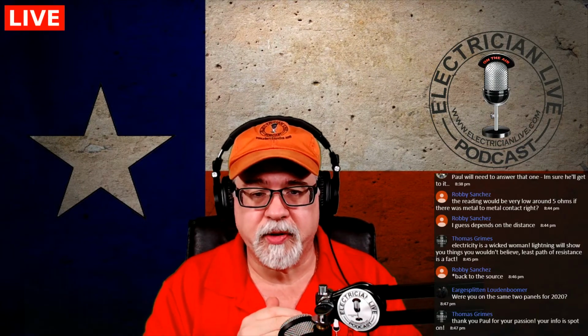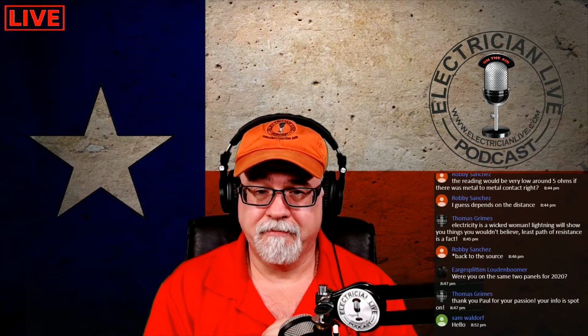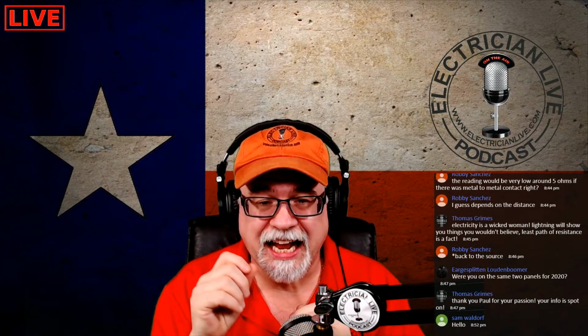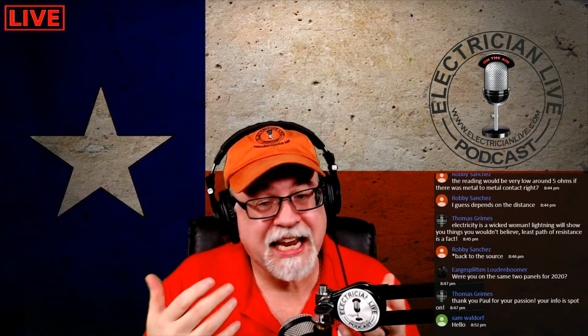I also had to do a test on NMB, and NMB has a bare conductor in it. Okay, you with me? And what I wanted to do is I wanted to put enough current through a conductor that was insulated, that was damaged, exposing the copper. And I wanted to see what it would take to create an arc from the insulated conductor over to the bare conductor in the middle of NMB. Now, the only thing separating is paper, right? Guess what? It took me about 5,000 volts in order to get it to bridge across that paper and spark so that I could measure it. So creating this takes a lot of voltage.